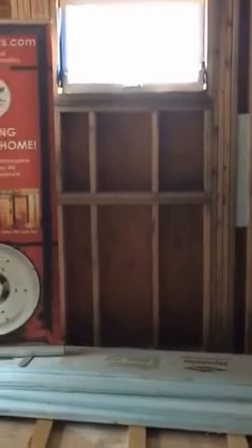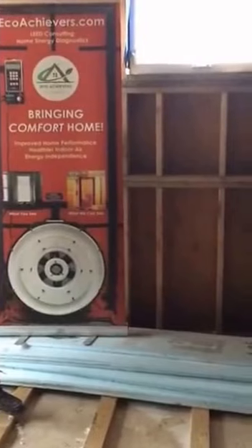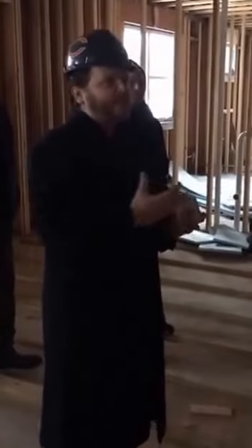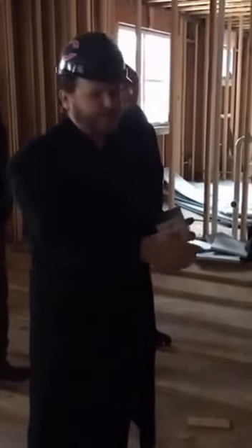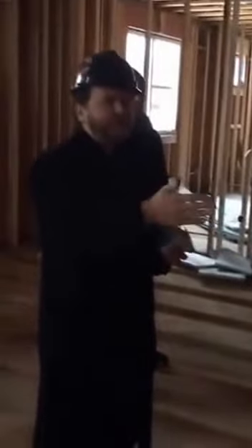The other side of that, though, is because this is a higher end space, they're actually putting in pretty high end appliances and range hoods. And we run into an issue when we see range hoods that are over 400 CFM being able to have adequate makeup air, so we're not backdrafting any other appliances or gurgling water out of the toilets or sucking up cats, right? So in this project, the other thing they're doing is they have a separate makeup air unit with a motorized damper that will open whenever somebody turns on the kitchen range hood to make sure that there's that balance of airflow and pressure in the space.